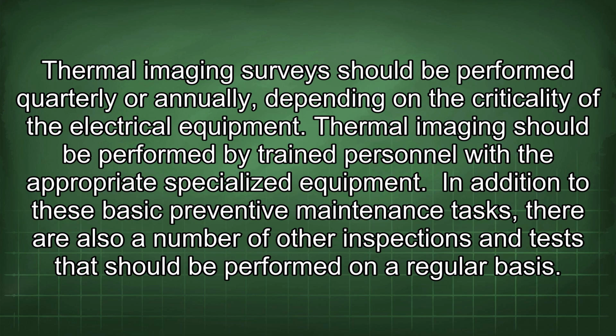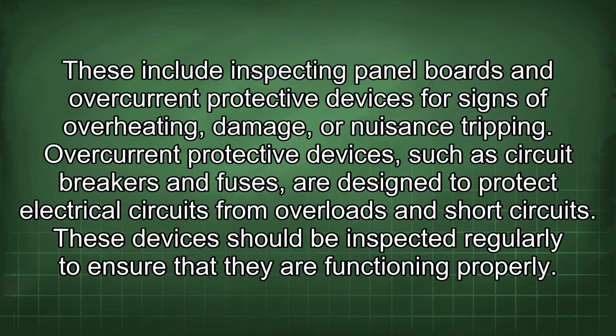Thermal imaging should be performed by trained personnel with the appropriate specialized equipment. In addition to these basic preventive maintenance tasks, there are also a number of other inspections and tests that should be performed on a regular basis. These include inspecting panel boards and overcurrent protective devices for signs of overheating, damage, or nuisance tripping. Overcurrent protective devices, such as circuit breakers and fuses, are designed to protect electrical circuits from overloads and short circuits. These devices should be inspected regularly to ensure that they are functioning properly.